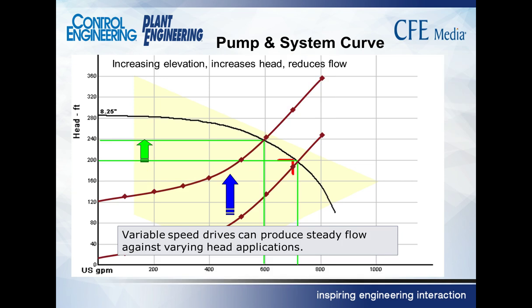Another advantage I think is just worth mentioning here: one of the problems that you run across sometimes on controlling flow is that you're pumping out of a sump and you want to have constant flow. He wants to keep that flow out of that beer vat at 600 gallons per minute, but as he's pumping it out, the level in the vat drops from 15 feet down to 4 feet.